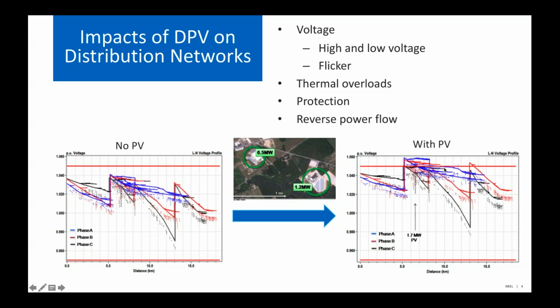So there are a few different effects that have been observed from distributed PV on distribution networks. These include voltage impacts, like high or low voltages, and voltage flickers, so variability in the voltage on the system. Thermal overloads on distribution lines or transformers. Issues with protection, protection coordination, for example, or anti-islanding. And reverse power flow. Since these networks weren't set up for reverse power flow, that can lead to issues with operation of devices on the grid. And in some cases, people have also started to see some backfeed at the substation.